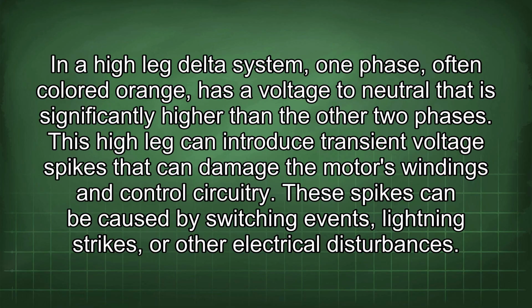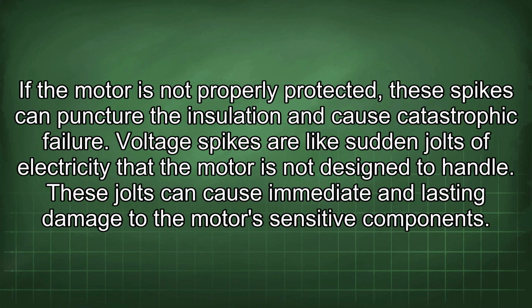These spikes can be caused by switching events, lightning strikes, or other electrical disturbances. If the motor is not properly protected, these spikes can puncture the insulation and cause catastrophic failure. Voltage spikes are like sudden jolts of electricity that the motor is not designed to handle. These jolts can cause immediate and lasting damage to the motor's sensitive components.